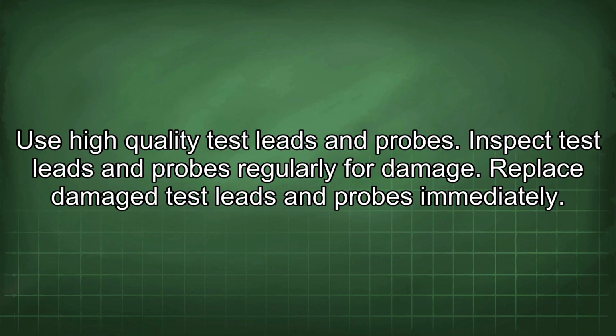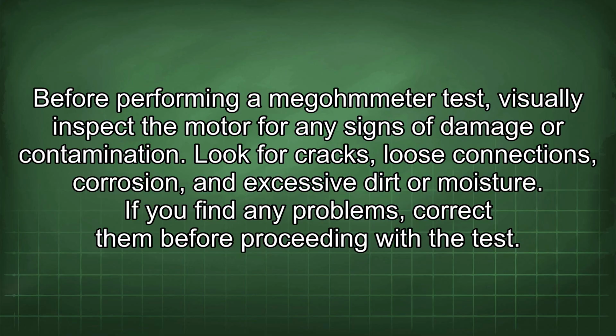Use high-quality test leads and probes. Inspect test leads and probes regularly for damage. Replace damaged test leads and probes immediately. Before performing a megohmmeter test, visually inspect the motor for any signs of damage or contamination. Look for cracks, loose connections, corrosion, and excessive dirt or moisture. If you find any problems, correct them before proceeding with the test.